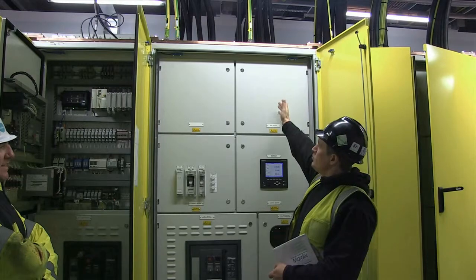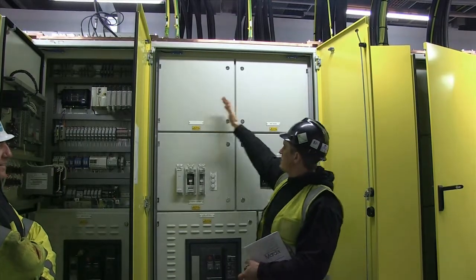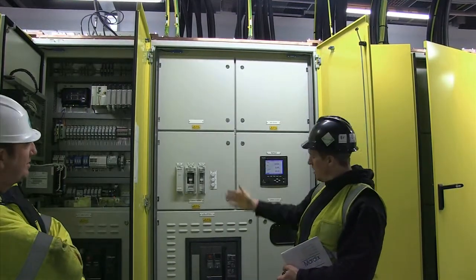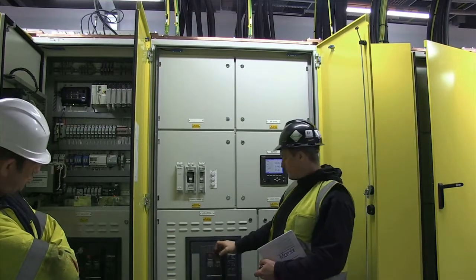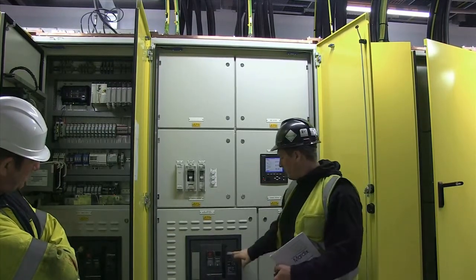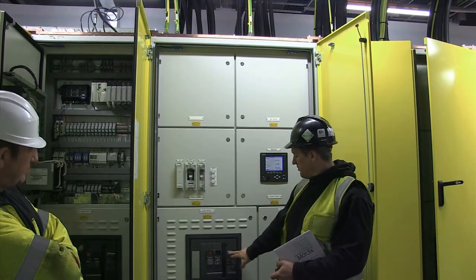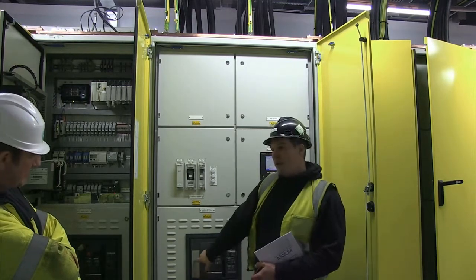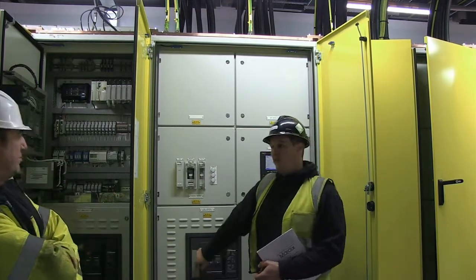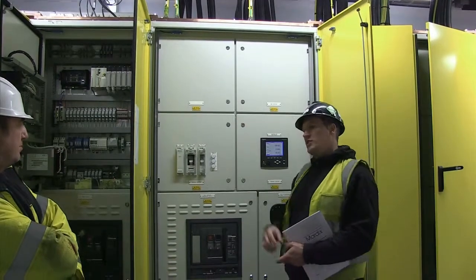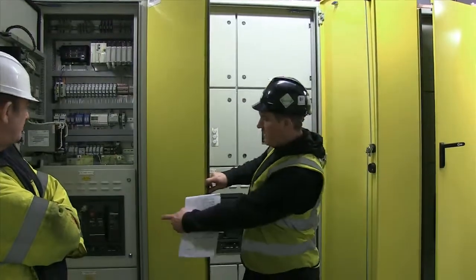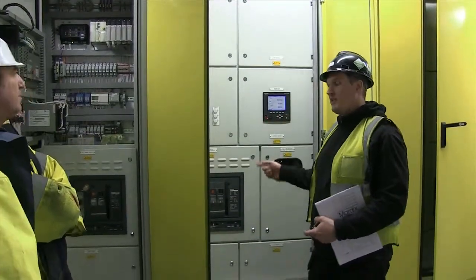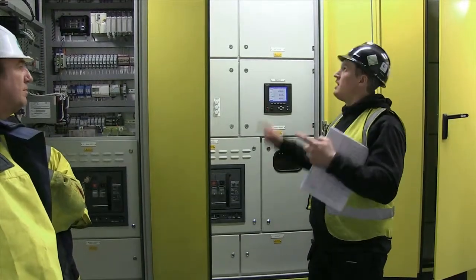On your generators, dual fed generators, so you've got two supplies coming in and it goes down to a parallel bar and it goes onto this connection here. This is your generator breaker. This breaker, like I said, is different because it's an NW25HF. No trip unit, there's nothing that will trip that in the event of a fault. However, the other end of the generator, they will have a breaker just like that with a trip unit on it. So if there's any fault, it gets picked up at that end, so it protects that cable.